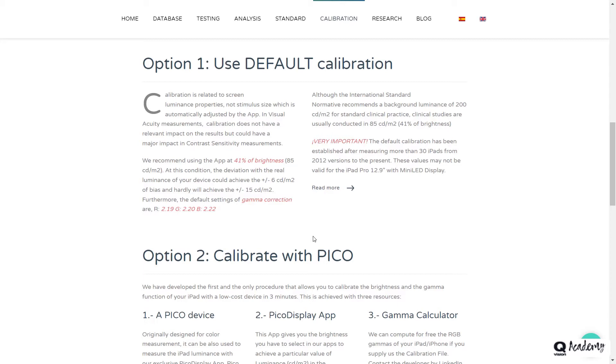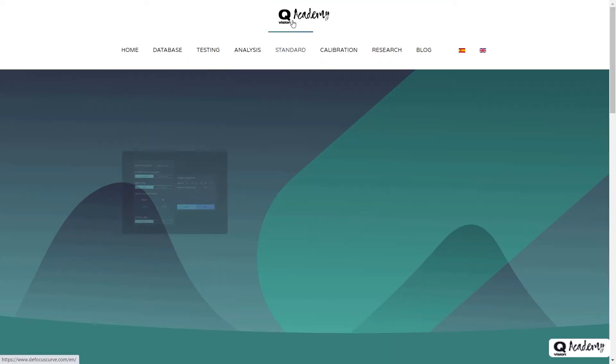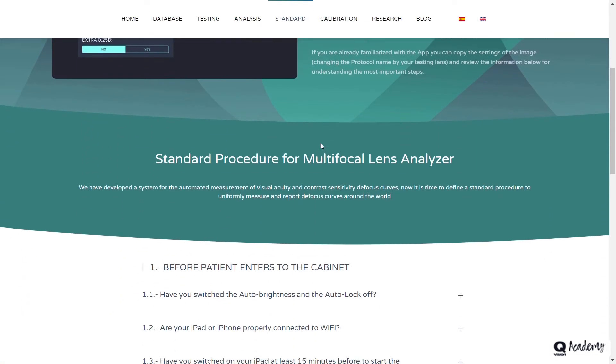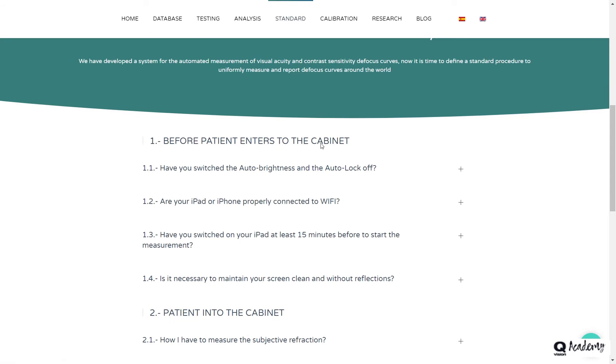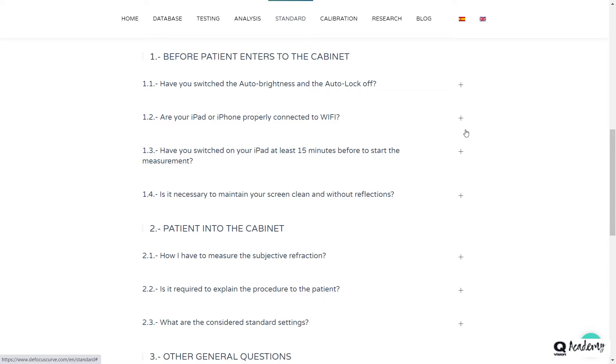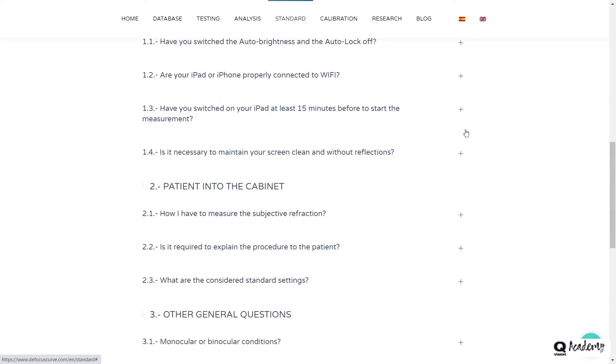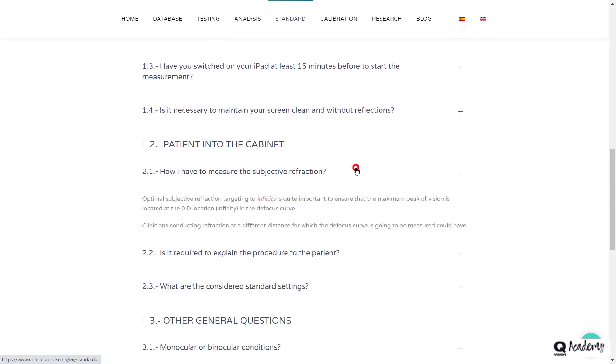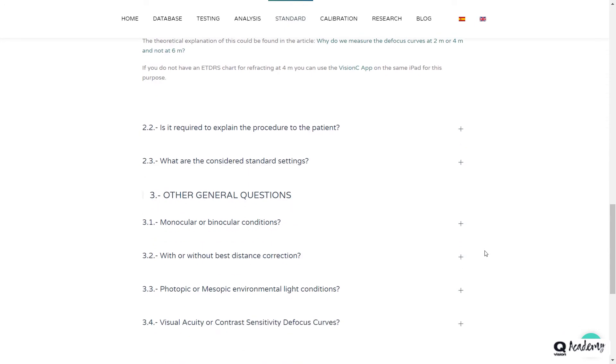Before starting any kind of research, please carefully review the standard section of our website to set up your protocols according to the measurement standards. Check that both the automatic brightness of your iPad and sleep mode are turned off, that you have turned on the iPad about 15 minutes before starting the measurements, and extremely important that the refraction that you will insert in the additional section is set to infinity. This is the most common error, which is why the defocus curves often appear offset from the zero diopters point. Please read this entire section carefully before starting to use the application.